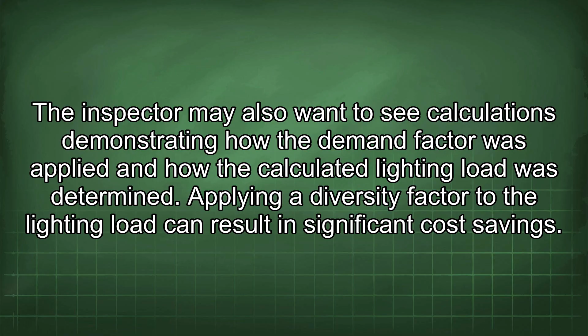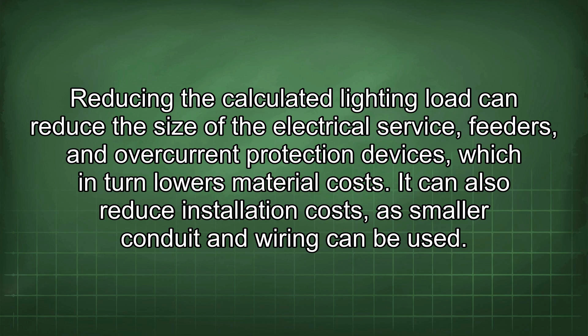Reducing the calculated lighting load can reduce the size of the electrical service, feeders, and overcurrent protection devices, which in turn lowers material costs. It can also reduce installation costs, as smaller conduit and wiring can be used. Furthermore, reducing the electrical service size can improve energy efficiency, as the electrical system will operate closer to its optimal loading point.